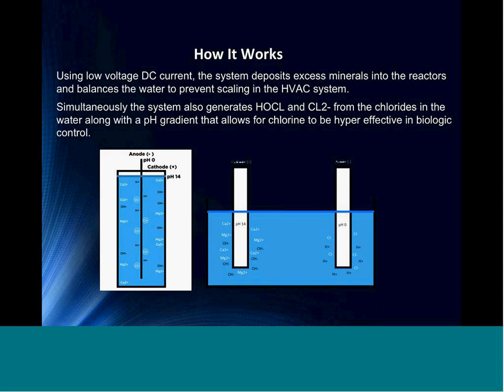This is, again, just a quick cutaway or overview of what we're doing. So we're putting low voltage DC current. We take 110 volt single phase into our power transformer, convert that to DC current, and we're using a maximum of 16 amps DC to create partial electrolysis in our system. And so as I said on the prior slides, we're doing 2 things.